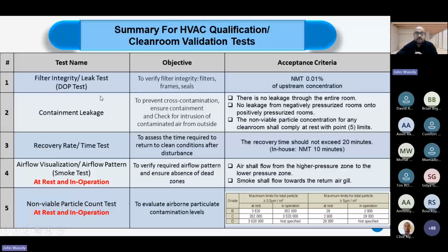By, for example, mentioning the containment leakage test, this is a very important test in order to prevent any cross-contamination, especially if we are talking about a vaccine manufacturing facility, because the vaccine is usually a hazardous product, and I don't want any escape from the less pressurized room or the hazardous room to the surrounding or adjacent rooms. So by this test, I make sure that the clean room in which I'm manufacturing my hazardous vaccine product is tightly sealed with no leakage, and no leakage is present from the negatively pressurized rooms onto the positively pressurized rooms.